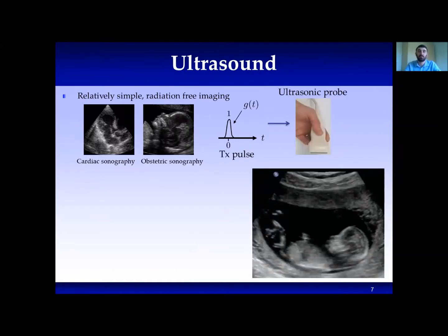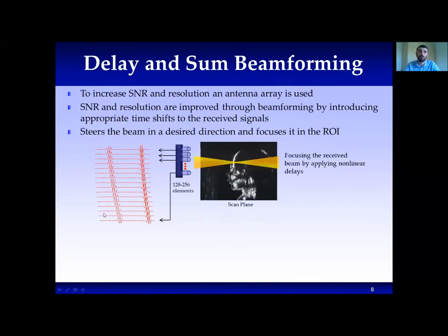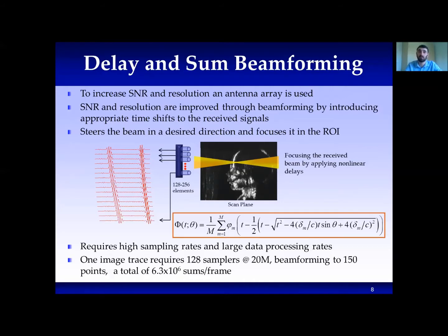Ultrasound imaging is performed by sending a pulse to the tissue. Echoes are then received from scattering elements in the tissue, with time delays corresponding to their depth. The final image is formed line by line based on the direction and amplitude of the scatterers. The most common method used is delay and sum, where an array of transducers is used, resulting in better SNR and image resolution after applying appropriate time shifts to the received signals.